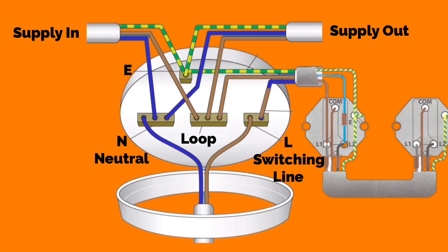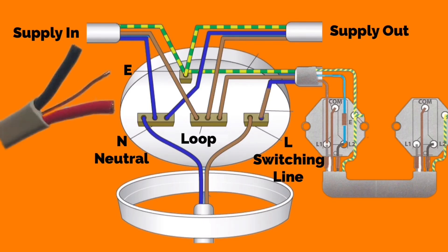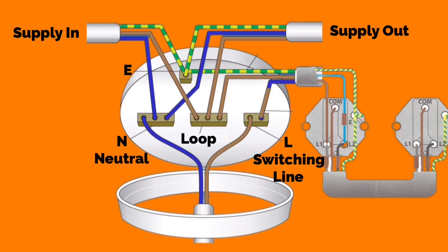When working in ceiling roses and pendants in domestic dwellings, you may also be faced with cable colors pre-2004. Pre-2004, the line conductor was red, the neutral conductor was black, and the circuit protective conductor was identified with green and yellow sleeving. The process is identical - care must be taken to make sure you're familiar with both new and old colors when making the appropriate connections.